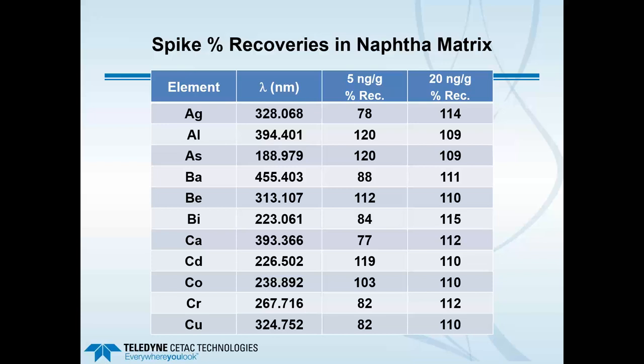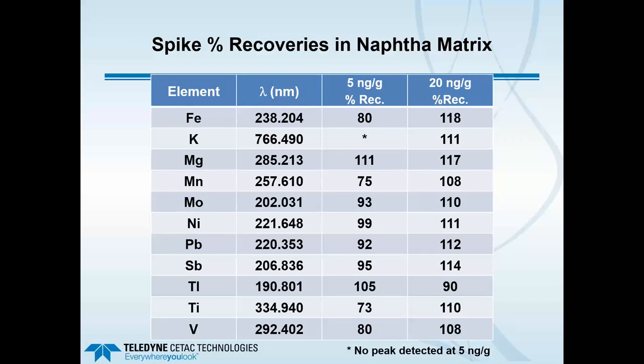For spike recoveries, our lowest calibration standard is 20 nanograms per gram. We pushed down to 5 nanograms per gram — four times lower — and still achieved good results. The recovery range was approximately 70 to 120 percent at 5 ng/g, and easily 90 to 120 percent at 20 ng/g. The one element with difficulties at 5 ng/g was potassium at 766.490 nm, which can be challenging at low levels. Overall, this was very good, especially for a spike of 5 ppb in liquid by weight.